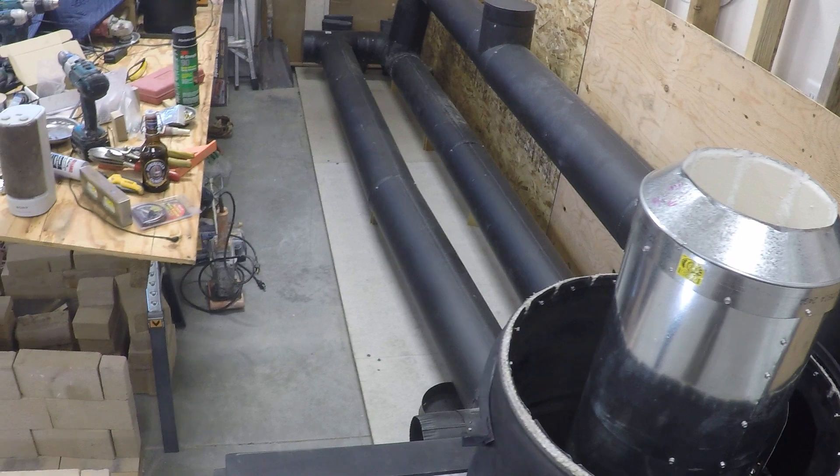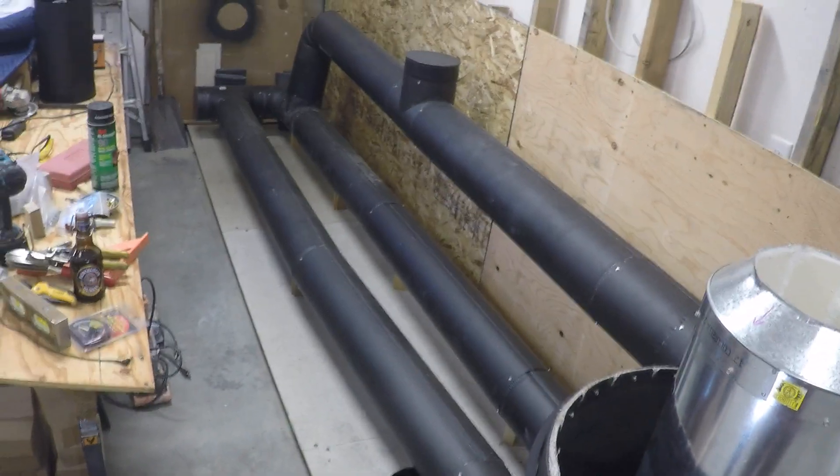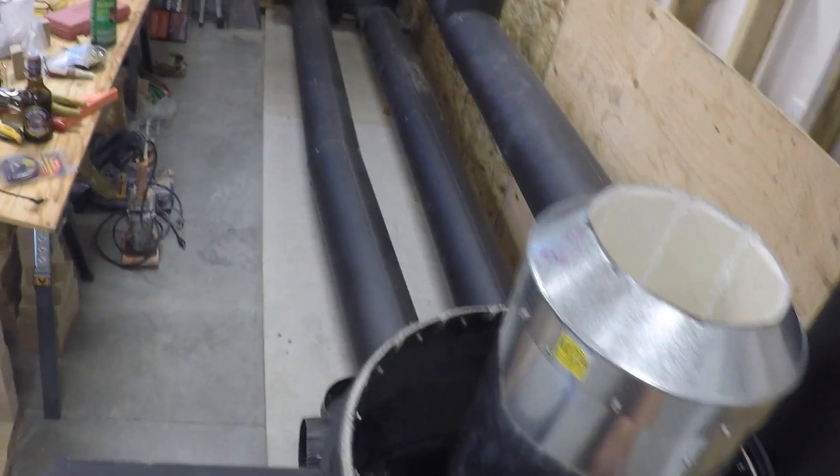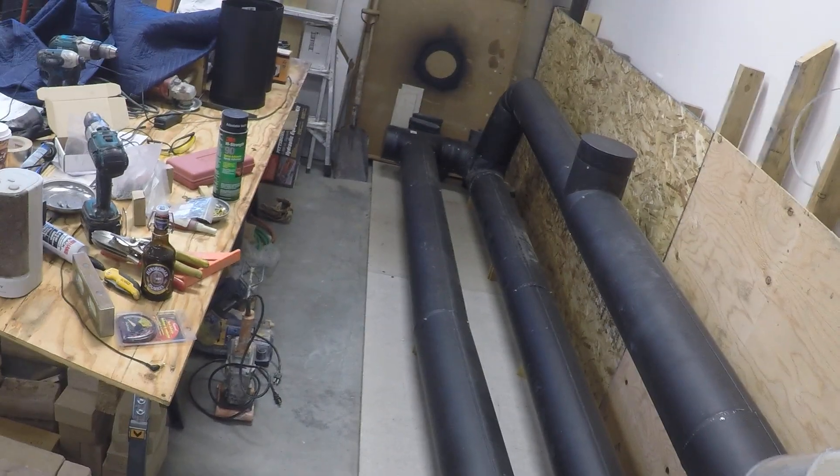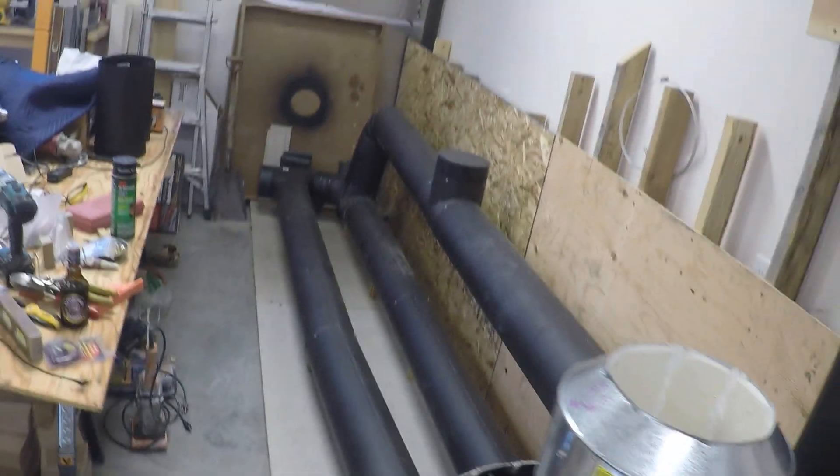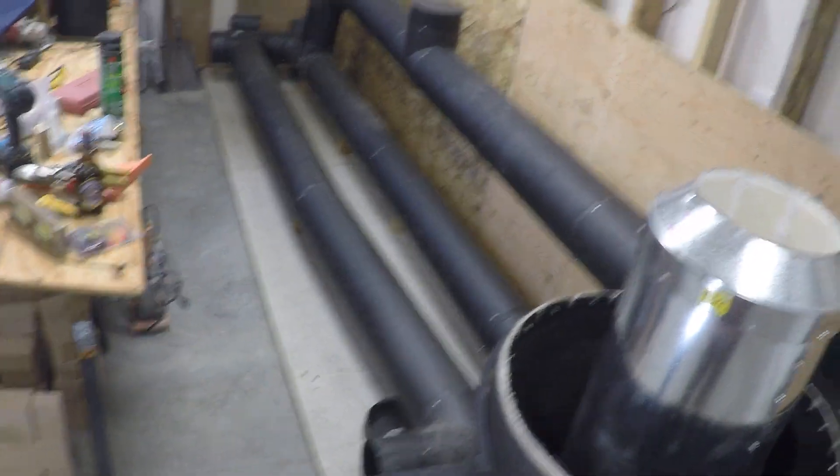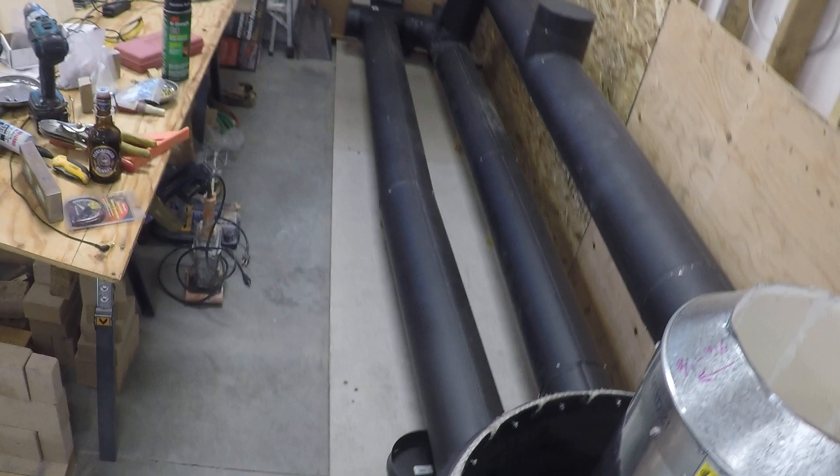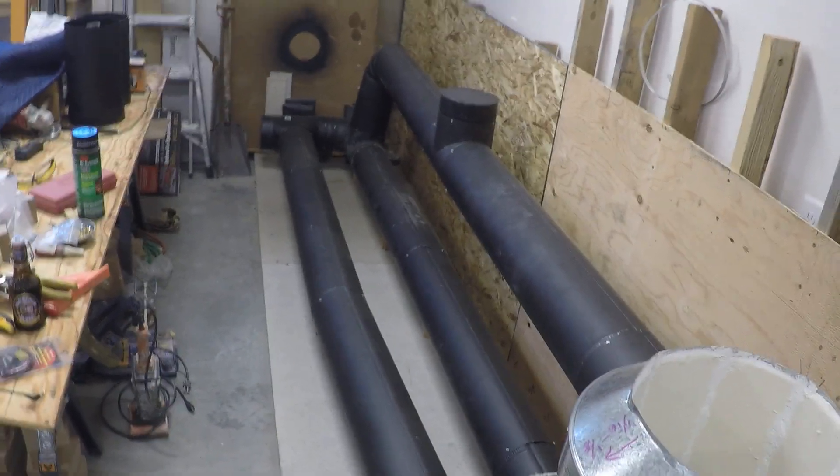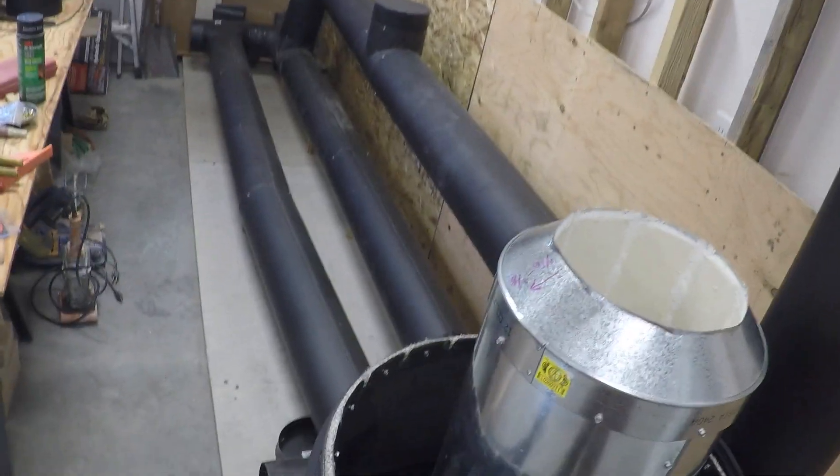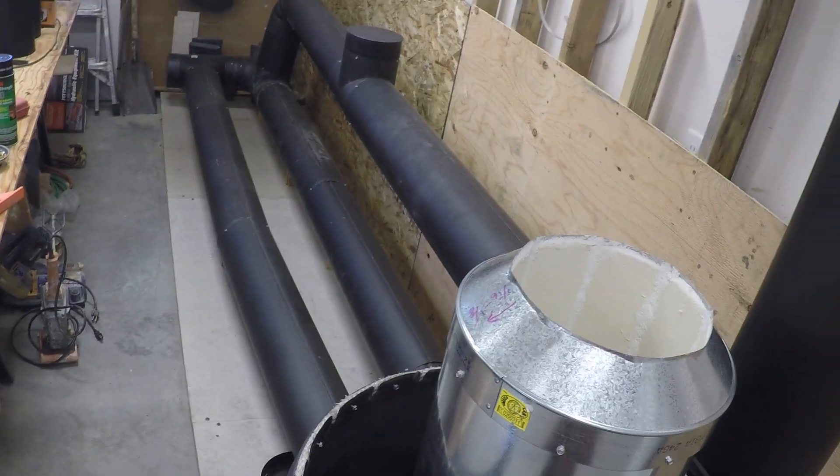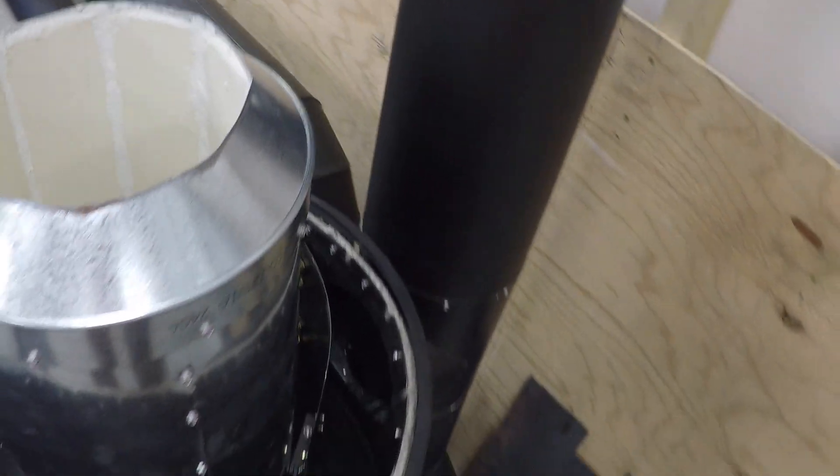But because we have a big bench and sideways duct run, if the bench is cold like the first start of the season, or because this is a shop and it might end up if people aren't in here a lot, it might lose all its temperature. The mass would release all its heat. Then you're doing a cold start again. And during shoulder season, which is really strong here in Montana, you got hot days and cold nights, and during that season you might need a bypass as well.